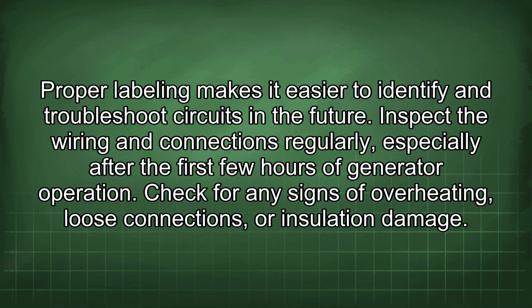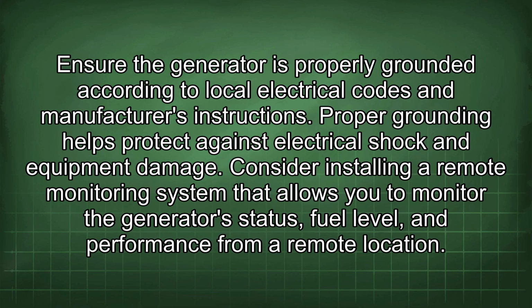Inspect the wiring and connections regularly, especially after the first few hours of generator operation. Check for any signs of overheating, loose connections, or insulation damage. Ensure the generator is properly grounded according to local electrical codes and manufacturer's instructions. Proper grounding helps protect against electrical shock and equipment damage.